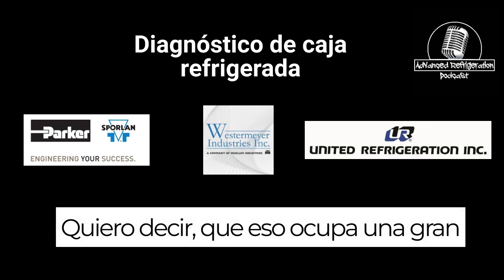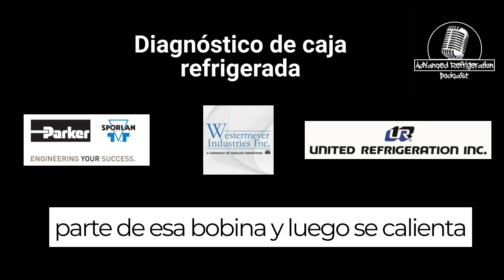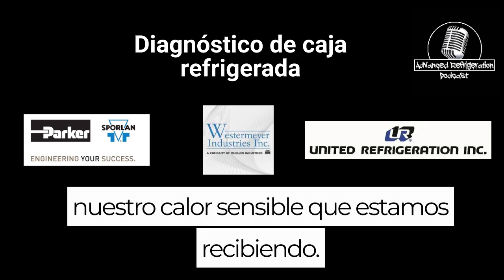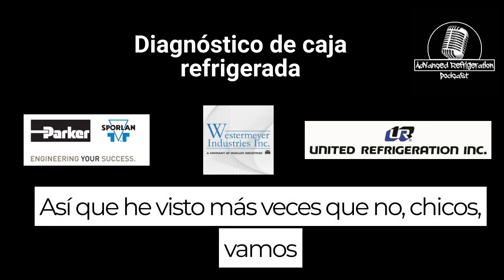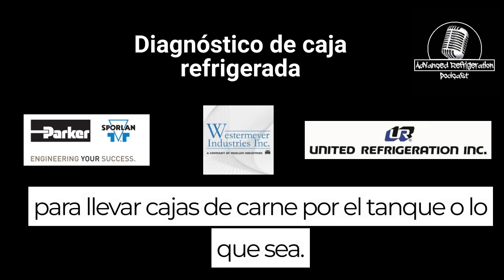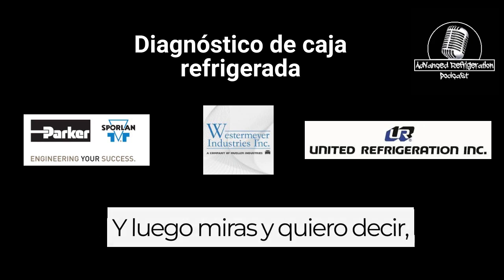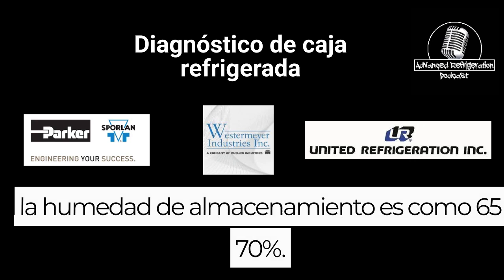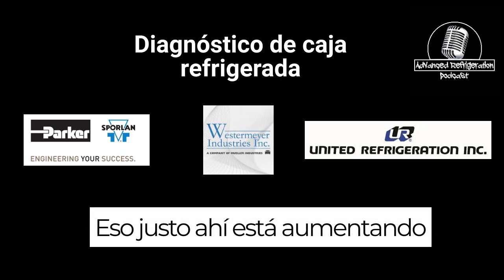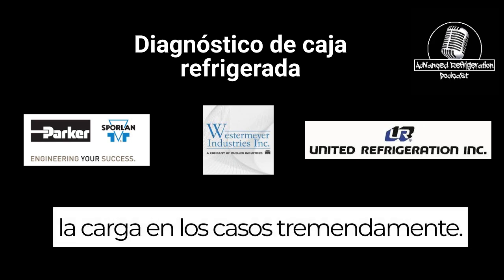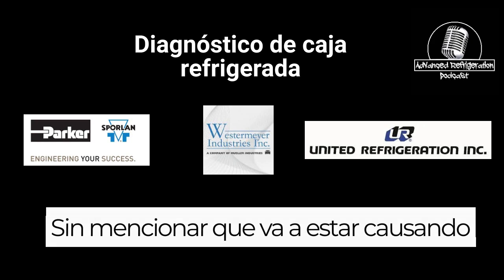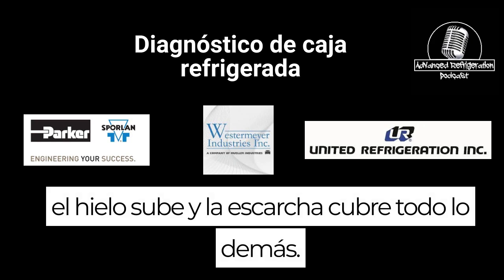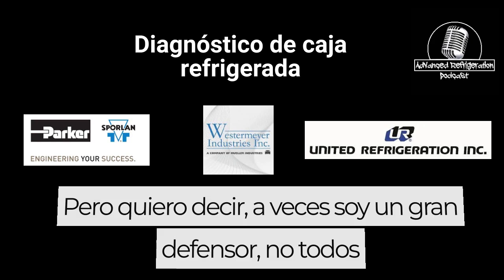I mean, that takes up a large portion of that coil, and then it eats up our sensible heat that we're getting. So I've seen more times than not guys working can't get meat cases down to temp, and then you look over and the stored humidity is like 65, 70%. I mean, that right there is just increasing the load on the cases tremendously. Not to mention it's going to be causing ice ups and frost overs, everything else.